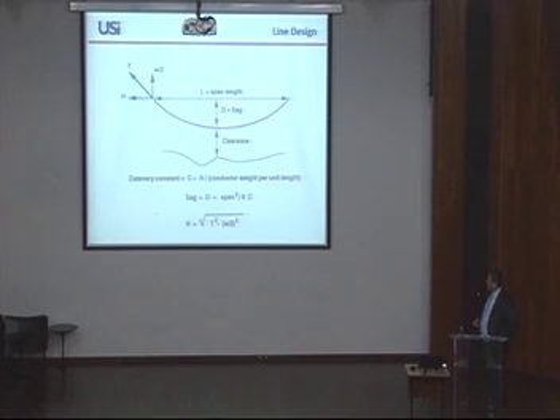So if you look at some other parameters from the line, you see the conductor here. This is the sag. That means how much the conductor drops to the ground, the clearance. So this sag is correlated to the tension of a conductor. You have to fix the conductor at the structure, and you need some tension to pull it. And there's a common parameter known as H/W, which describes the horizontal component of the tension and the conductor weight per unit length. And as you can see, and you surely know, the sag is corresponding to this constant H/W, and there are also two constants, the span length and a constant value. So sag and tension, the H here, are directly correlated.